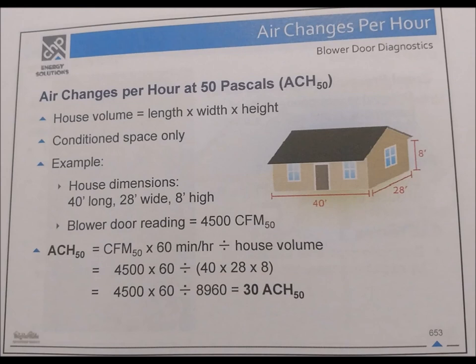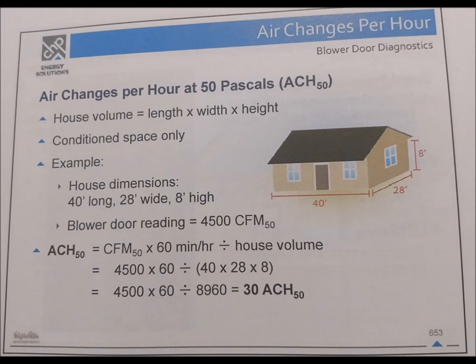Blower door — air changes per hour. ACH50 equals CFM50 times 60 minutes per hour divided by house volume (conditioned space only). House volume equals length times width times height. Example: House is 40 ft × 28 ft × 8 ft; blower door reading is 4,500 CFM at 50 pascals. ACH50 = 4,500 × 60 divided by (40 × 28 × 8) = 270,000 divided by 8,960 equals approximately 30 ACH50.